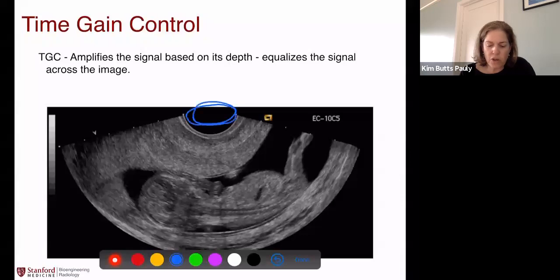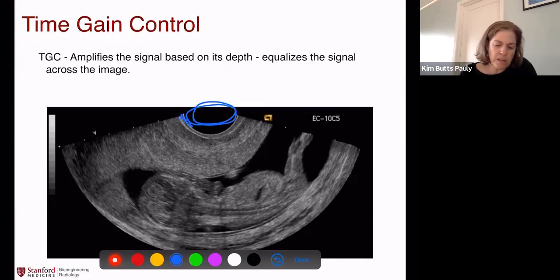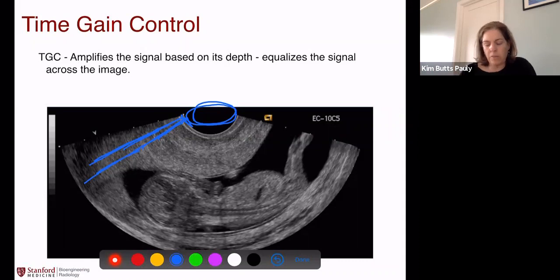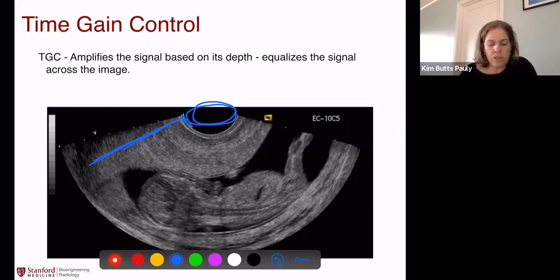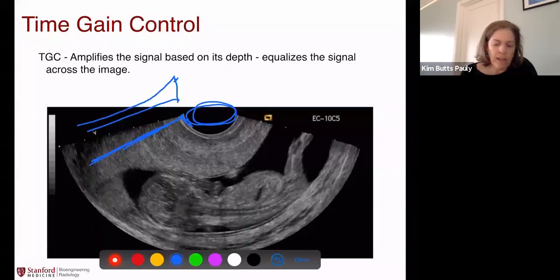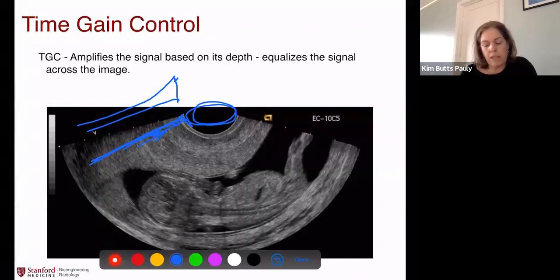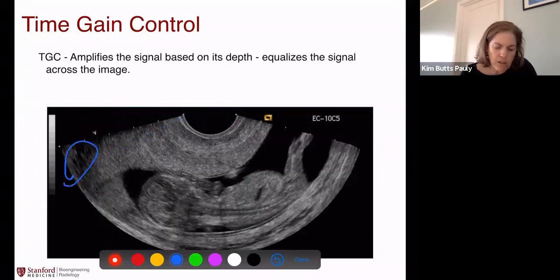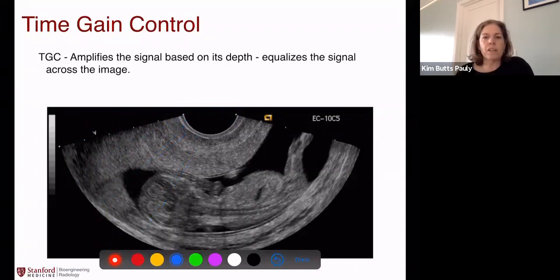They're always shown with the transducer up here, and the ultrasound is sent out. In this case, this is a curved planar transducer. We use a subset of the elements, send a beam out, and get reflections coming back from different depths. We send another one out, and as it goes through the tissue, we get reflections back. We count up all those reflections and make an image. Now, as the beam goes into the tissue, the signal is going to decrease — you'd expect the image to look darker and darker going deeper. And you do see some darkness down here, but generally it looks sort of flat gray, which is interesting. Why does it not appear attenuated?